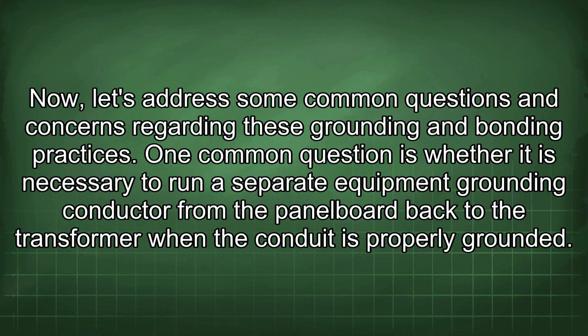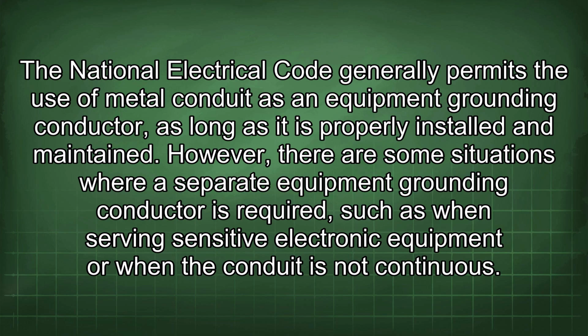Now, let's address some common questions and concerns regarding these grounding and bonding practices. One common question is whether it is necessary to run a separate equipment grounding conductor from the panel board back to the transformer when the conduit is properly grounded. The National Electrical Code generally permits the use of metal conduit as an equipment grounding conductor as long as it is properly installed and maintained. However, there are some situations where a separate equipment grounding conductor is required, such as when serving sensitive electronic equipment or when the conduit is not continuous.